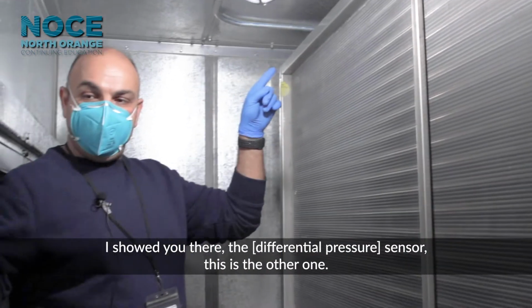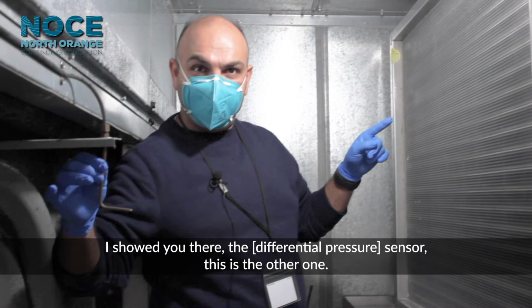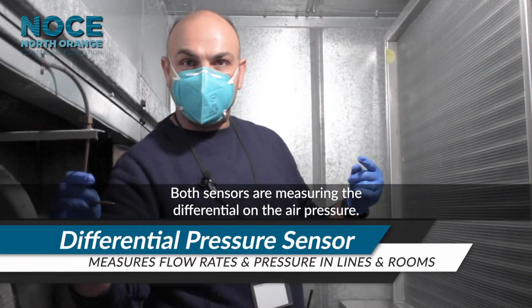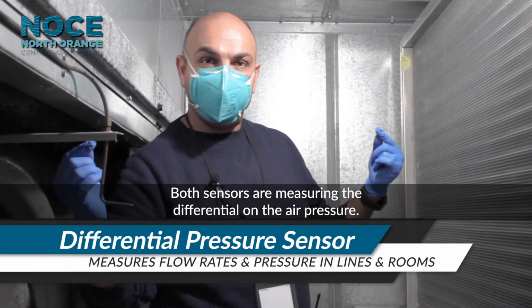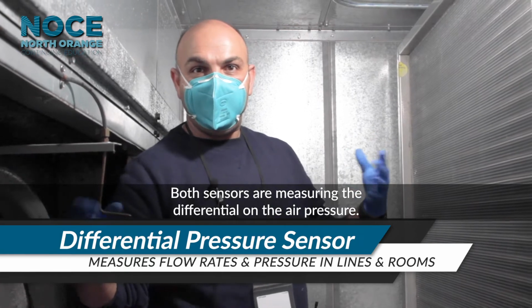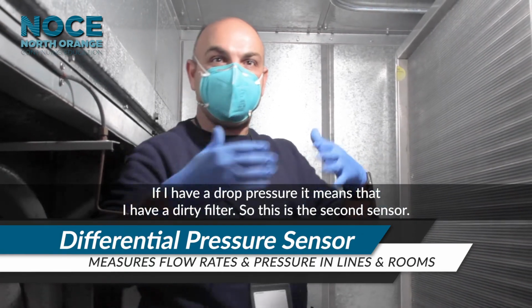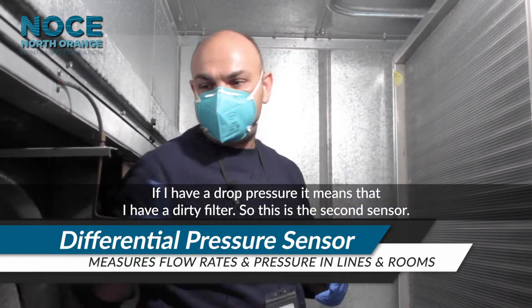So I showed you there the sensor, and this is the other one. So both sensors are measuring the differential on the air pressure. If I have a drop in pressure, it means that I have a dirty filter. So this is the second sensor.